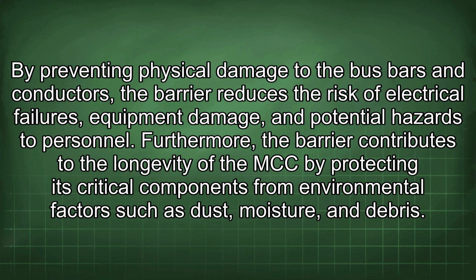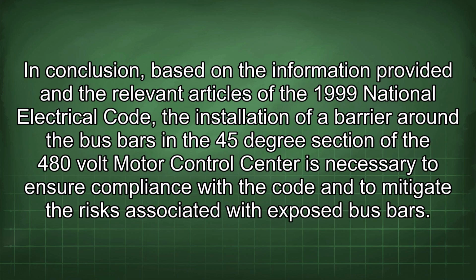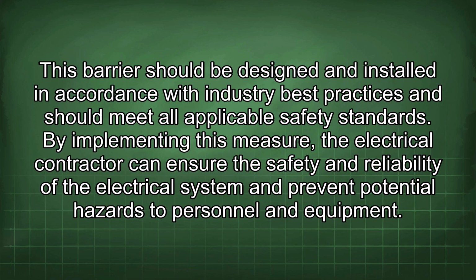Furthermore, the barrier contributes to the longevity of the MCC by protecting its critical components from environmental factors such as dust, moisture, and debris. In conclusion, based on the information provided in the relevant articles of the 1999 National Electrical Code, the installation of a barrier around the bus bars in the 45-degree section of the 480-volt motor control center is necessary to ensure compliance with the code and to mitigate the risks associated with the exposed bus bars. This barrier should be designed and installed in accordance with industry best practices and should meet all applicable safety standards. By implementing this measure, the electrical contractor can ensure the safety and reliability of the electrical system and prevent potential hazards to personnel and equipment.